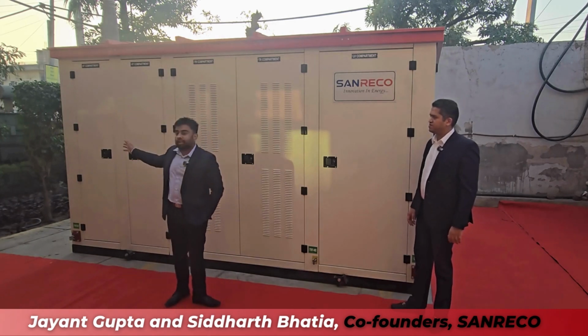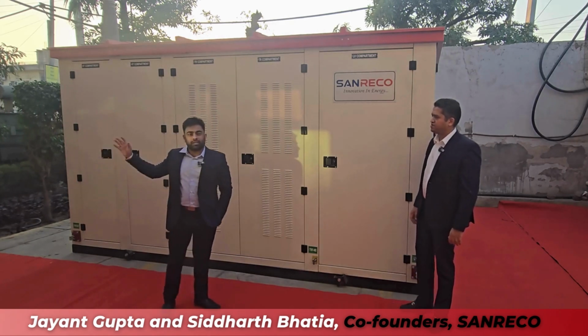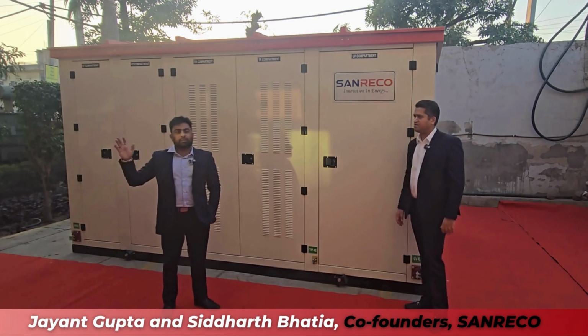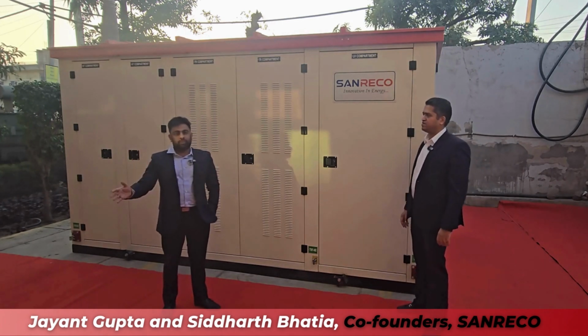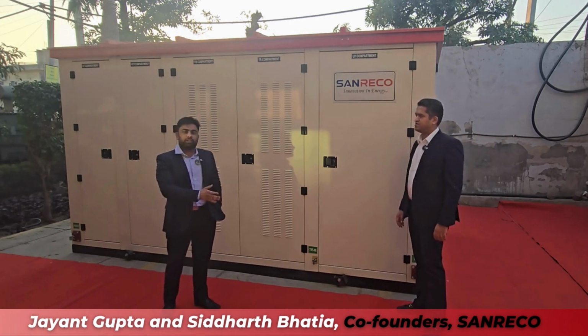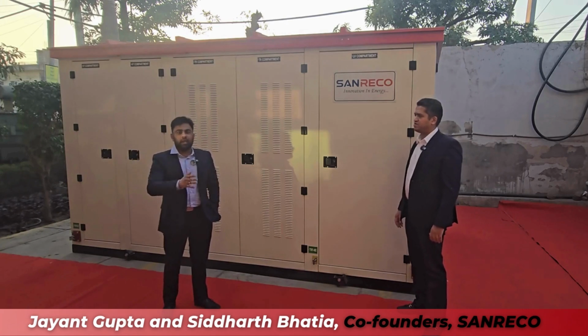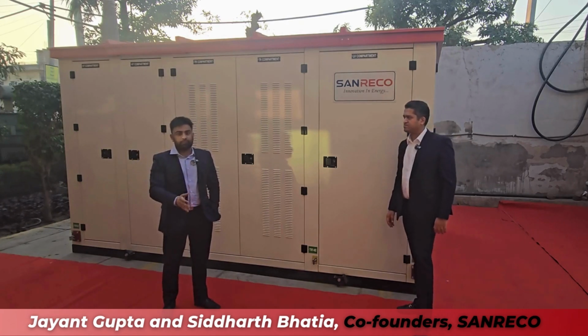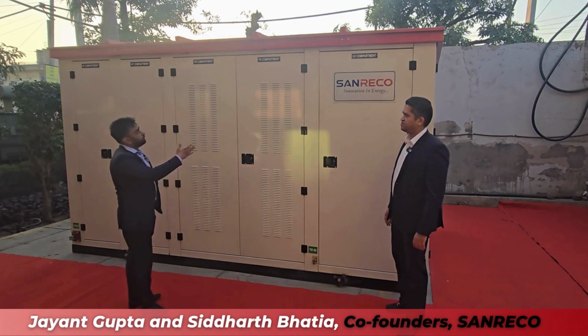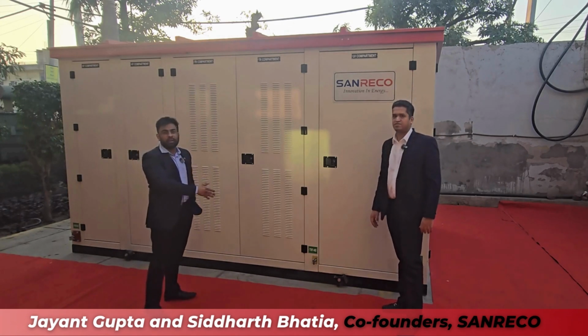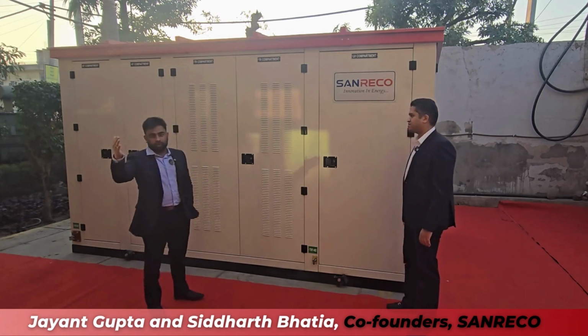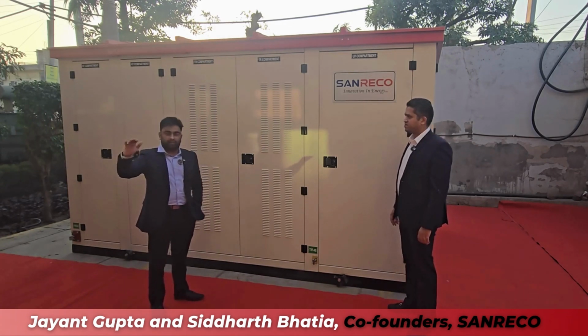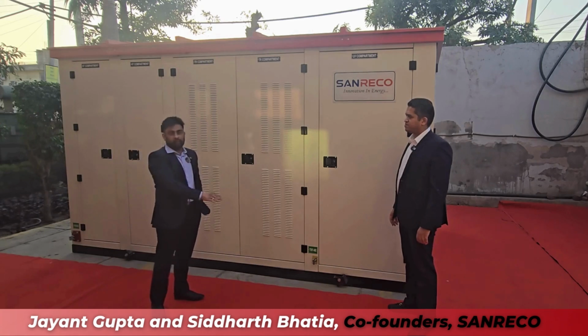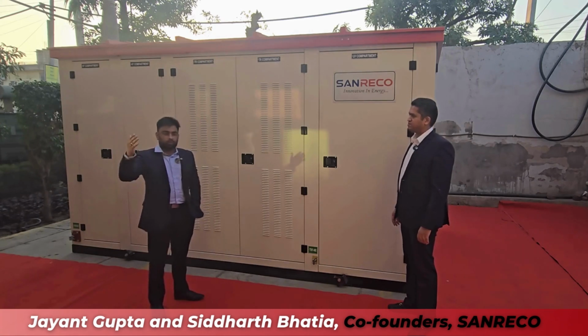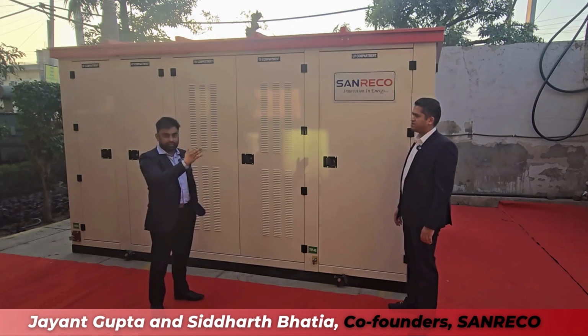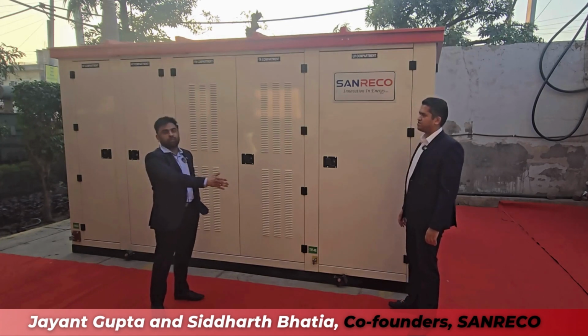The first is the HT compartment, the high tension compartment, which comprises the RMU VCB used for transformer protection as well as HT line fault protection. The middle compartment is the transformer compartment, which steps down the HT line to the LT line. So if your load is 11 kV or 33 kV, it steps it down to 415, 433 volts.